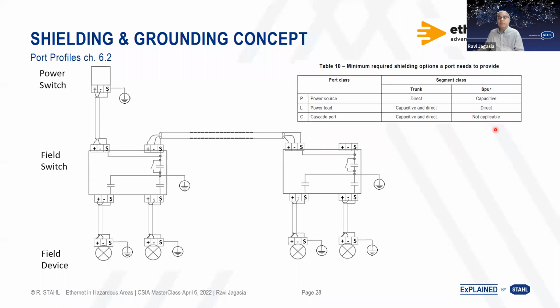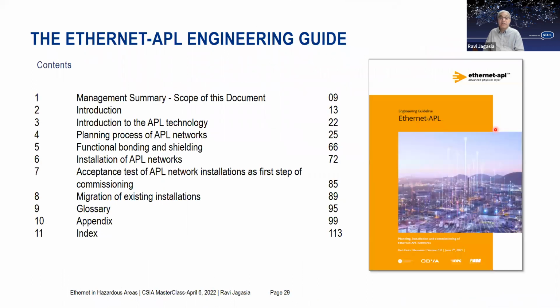You can of course read more of that, and when you design it, definitely you refer to the engineering guide. And the engineering guide is available online. The version, if I'm not wrong, this is the 1.1. Covering a lot of the requirements of implementing Ethernet-APL. You have the planning and the design process, the functions, the bonding over there, how you install the networks, what is the acceptance test you need to do to confirm when you hand over the network or the installation to the end user, and possibly some options of migration. Of course, there is a lot of options there for migrations, and that is something we can look at later also.